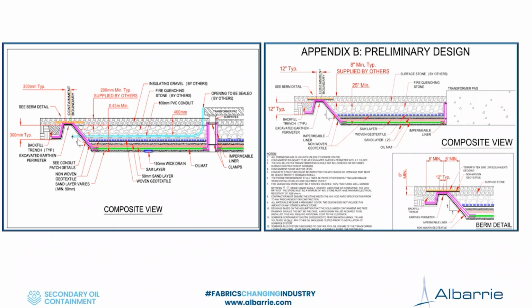So as you saw in the previous slides, the containment is very flexible. So if you have infrastructure like conduits, direct buried cables, grounding grid, we can accommodate all of those things either by incorporating them into the containment system or booting and sealing around them. Or if you can bury the cables or conduits or grounding grid below the containment and have them come up the pad, obviously that's the preferred method, because it reduces the amount of intrusions or punctures you put through the containment.